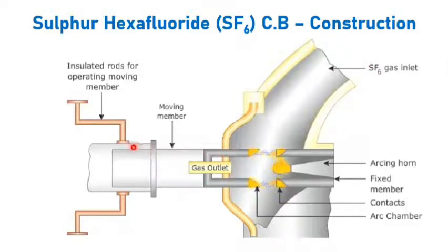So this is the moving contact and this is the fixed contact. Moving and fixed contacts are hollow cylinders. They have holes on their sides and they are coated with tungsten, and there is a reservoir for keeping the SF6 gas stored. When the contacts are closed, the surrounding space between the contacts will be filled with SF6 gas at some pressure, and a separate reservoir is used for storing the SF6 gas.